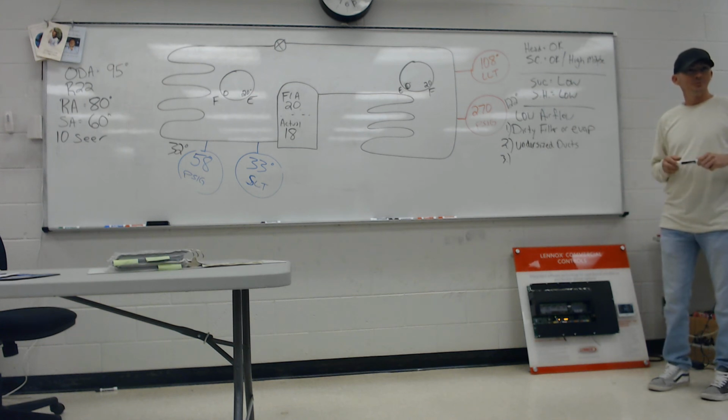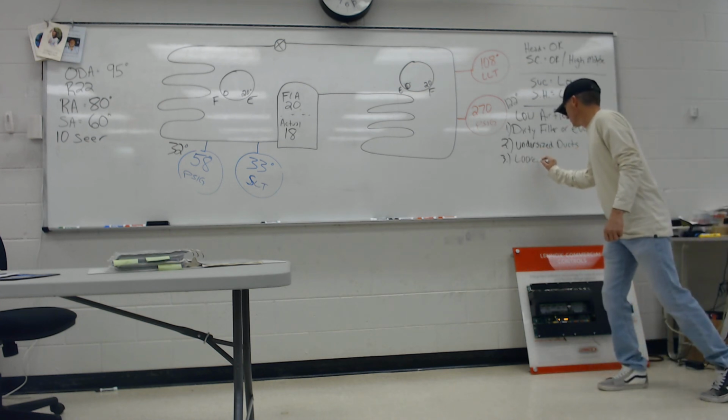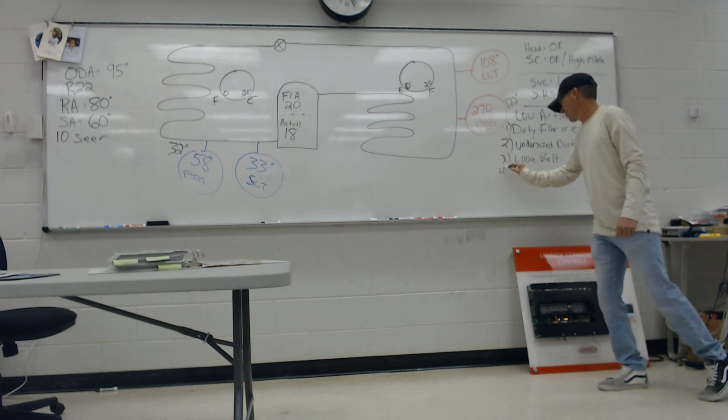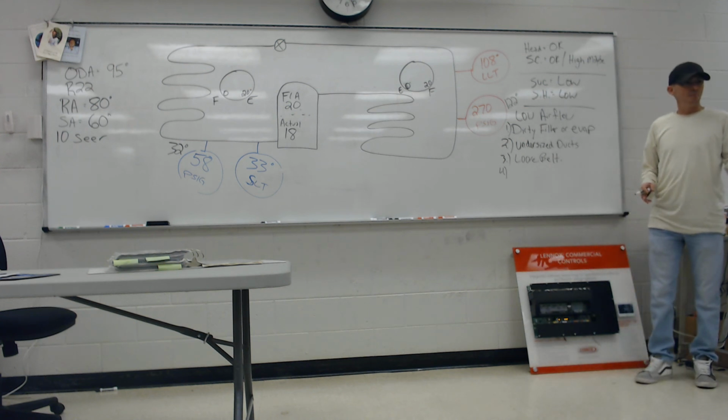What if it's squealing real bad? What are you going to be checking as soon as you take that panel off? Belt. Loose belt. Non-existent belt, yeah. You can start getting deep, like if it's variable frequency driven, maybe it's not ramping up to whatever speed it's supposed to. What is some more just common stuff though?